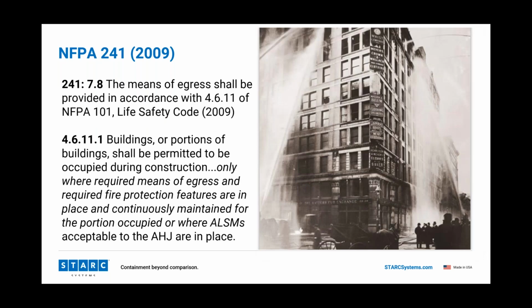241 also says when you have a means of egress for construction, that the means of egress has to be in accordance back to NFPA 101 Life Safety Code, right? So, and it says in there only where required means of egress are required by fire protection features, they have to be continuously maintained, right?